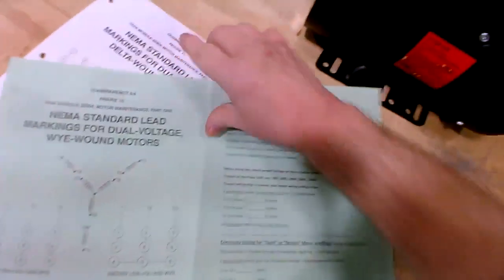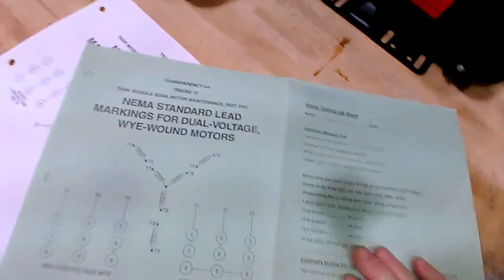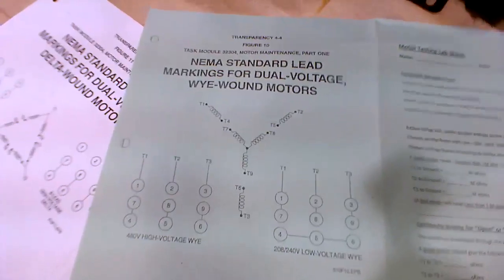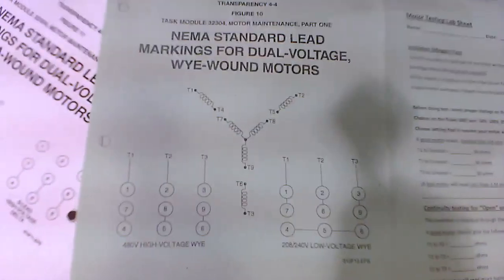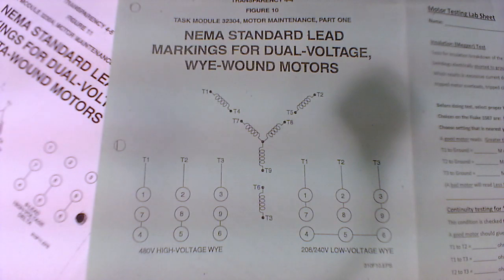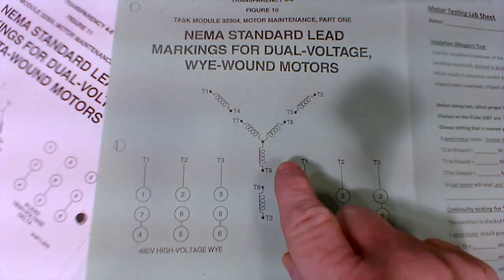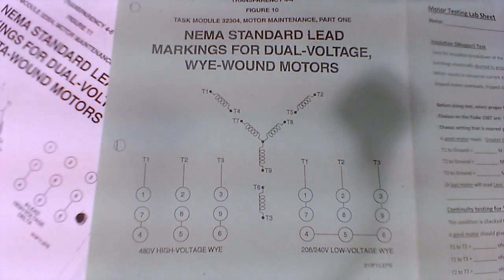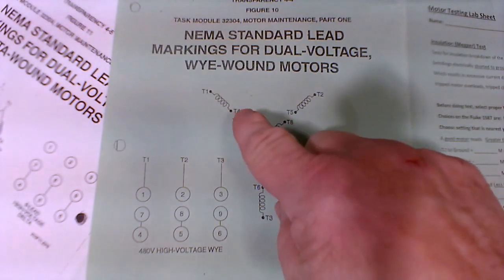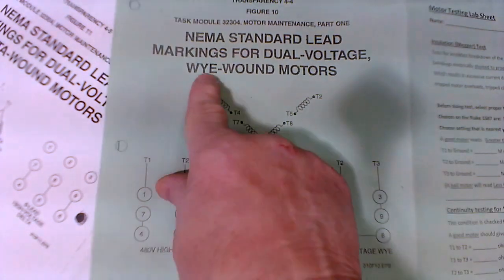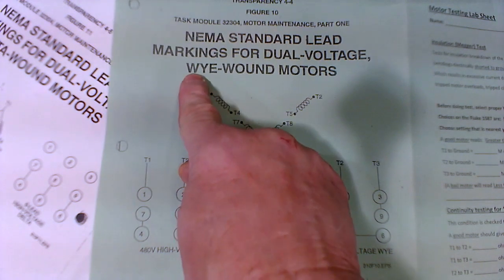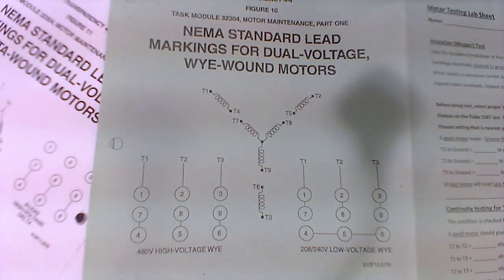let's look at two general types of motor windings that are most common in the industry. And most motors I've been around over the years, from where I've worked, in a couple plants, most of the motors were considered to be internally, this is a three-phase motor over here, most of them were considered to have a configuration of windings called Y. It's a WYE, that's the proper way to say that. It's a Y-wound motor, and it's shaped like the letter Y on the inside.